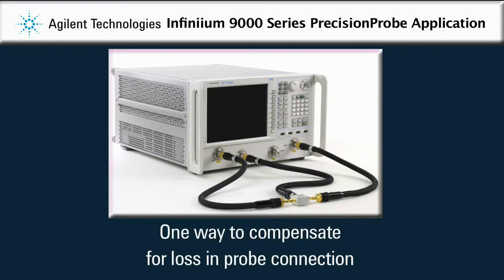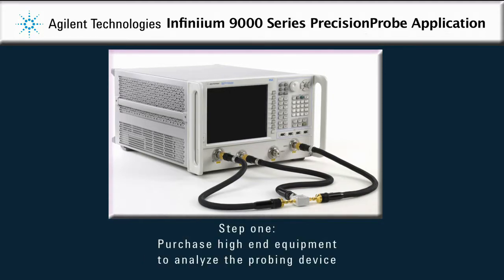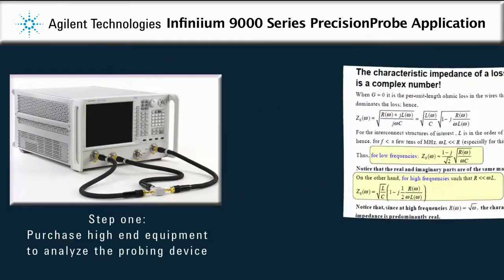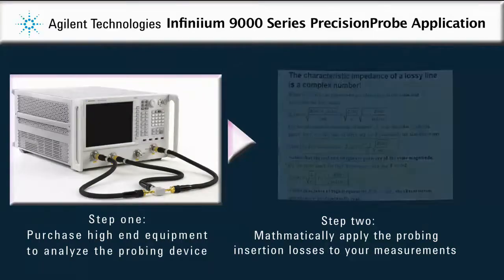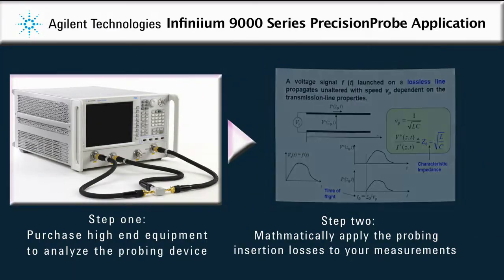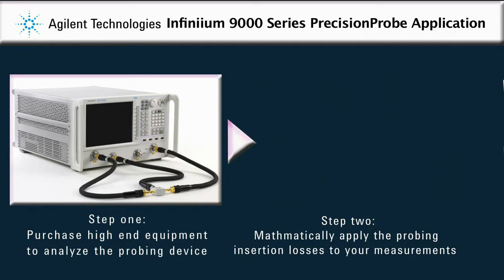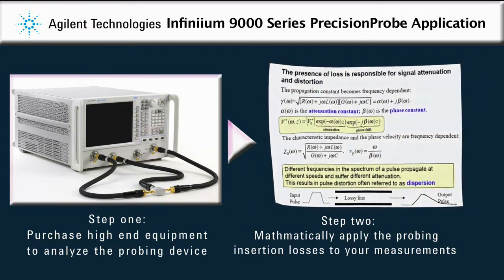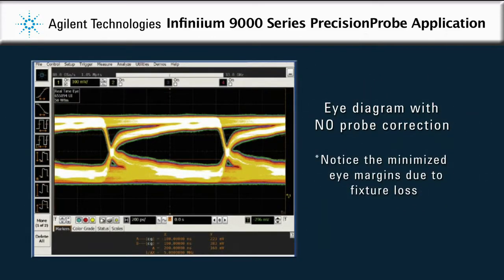This compensation has traditionally been done using high-priced vector network analyzers to measure probe responses and then uses mathematically modeled results. This can be time-consuming, expensive, and requires a high level of specific skill. Many engineers choose to forgo this difficult and costly process and therefore live with measurement inaccuracy associated with their probing devices.